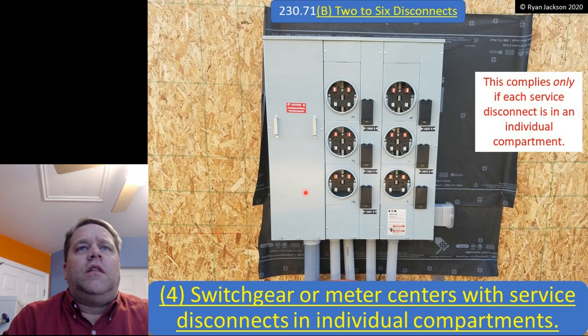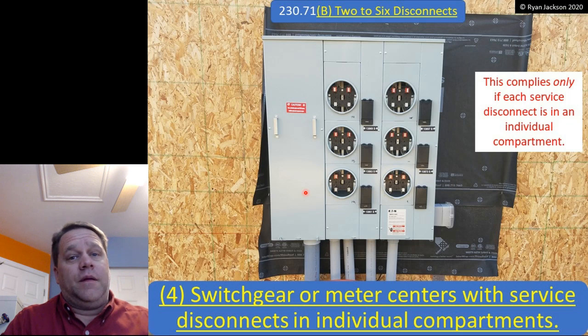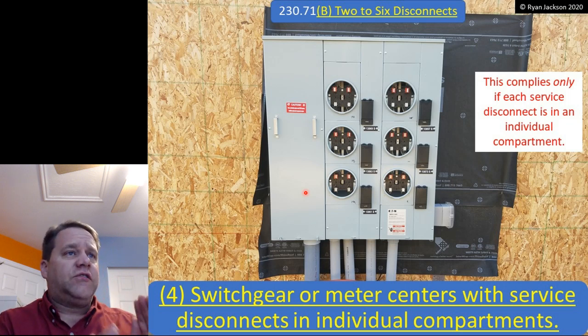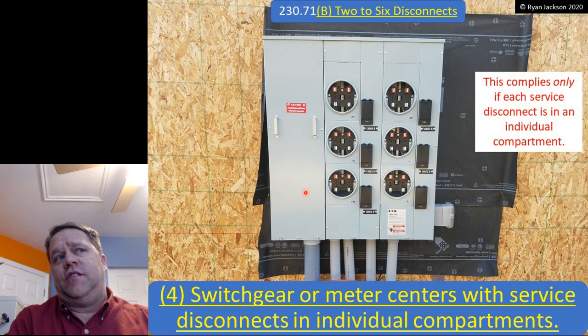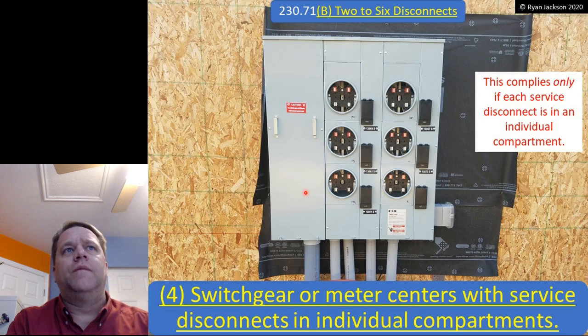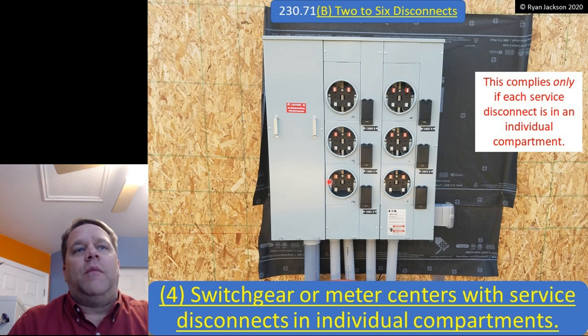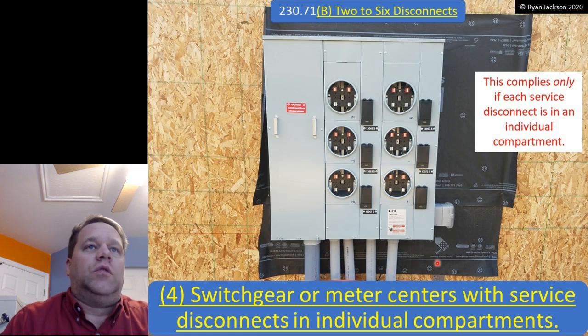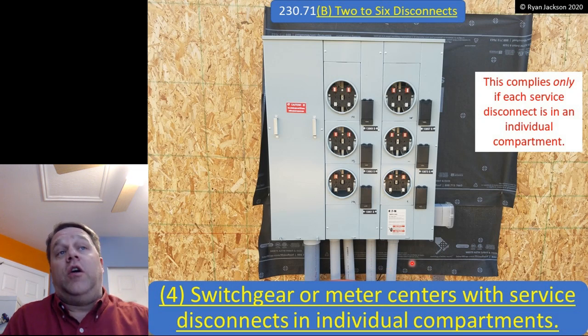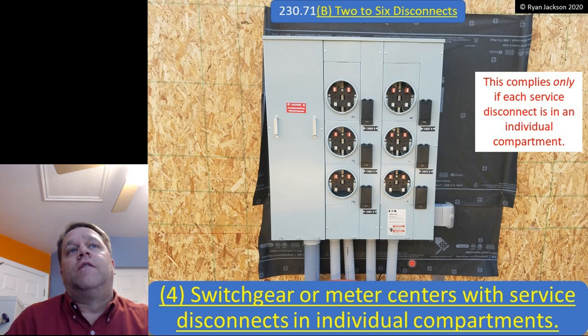The other time that I can have multiple disconnects is for switchgear. And by the way, let's push pause here. If I have switchgear as my service disconnect, be very careful because it has to be marked as suitable for use as service equipment, SUSE, and most switchgear is not. So be careful with that. But switchgear, or more commonly, meter centers with service disconnects in individual compartments. Okay, this is a very common sight, at least in my area, for multifamily dwellings.